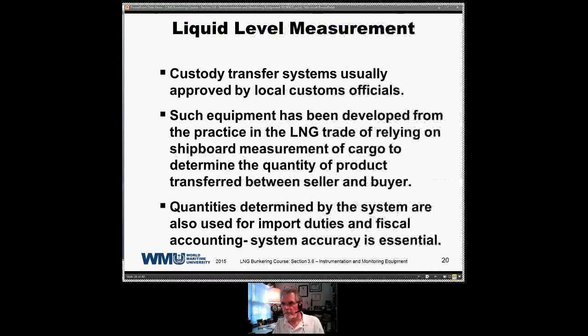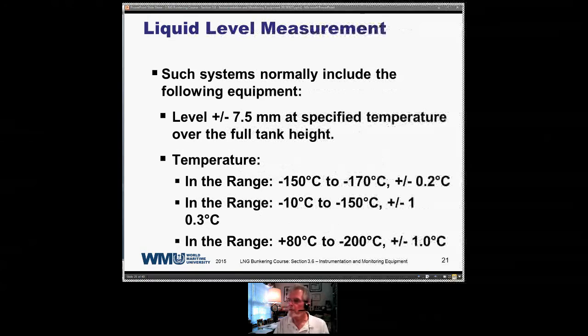Okay, such systems include the following equipment. You have a level gauge which is accurate to plus or minus 7.5 millimeters at a specified temperature over the full height of the tank. So you're looking at plus or minus 7 millimeters over a 35-meter tank. In the case of a spherical ship, and in the case of membrane ships, you're looking at an accuracy of approximately the same over a distance of 25, 26 meters perhaps.